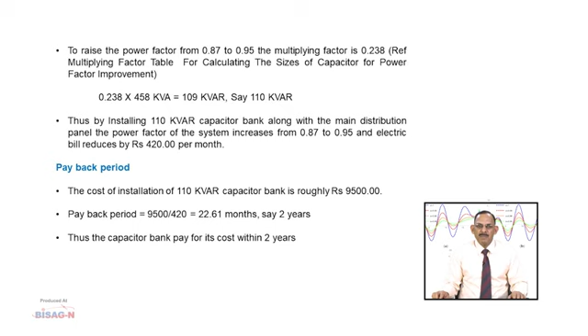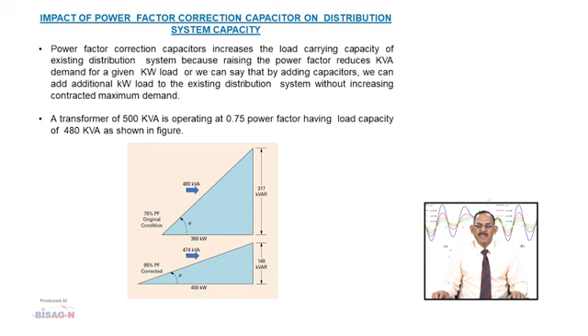Impact of power factor correction capacitors on distribution system capacity. Power factor correction capacitor increases the load carrying capacity of the existing distribution system because raising the power factor reduces kVA demand for a given kW load. Or we can say that by adding capacitors we can add additional kilowatt load to the existing distribution system without increasing contracted maximum demand. A transformer of 500 kVA is operating at 0.75 power factor having load of 480 kVA as shown in the figure. The actual working power from this transformer is only 360 kilowatt, that is 480 kVA into 0.75. It is desired to increase the load up to 450 kilowatt on the same transformer due to construction of new officer accommodations or some other expansion. This can be achieved by improving the power factor from 0.75 to 0.95 instead of replacing the transformer.